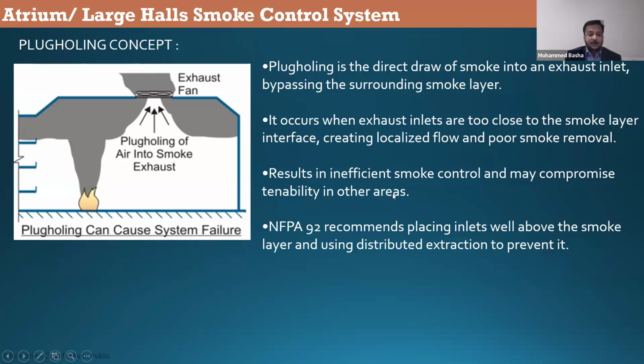So you need to know how many fans I need to use. Okay, the total volumetric flow rate is this much. Can I achieve it by one fan, or do I need multiple fans, or one fan with one inlet, or one fan with multiple inlets? Sorry, multiple extracts. NFPA 92 recommends placing inlets well above the smoke layer and using distributed extraction to prevent it. That is called the plug holing approach.